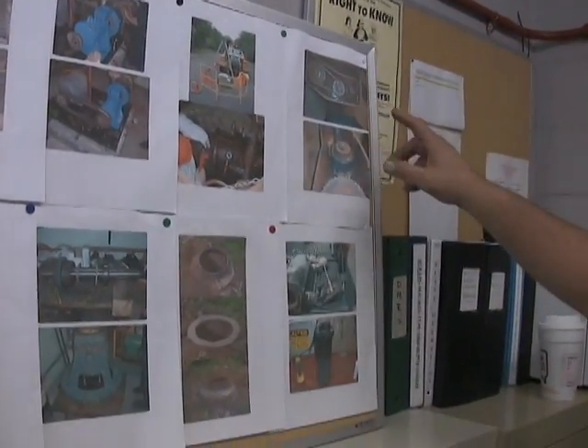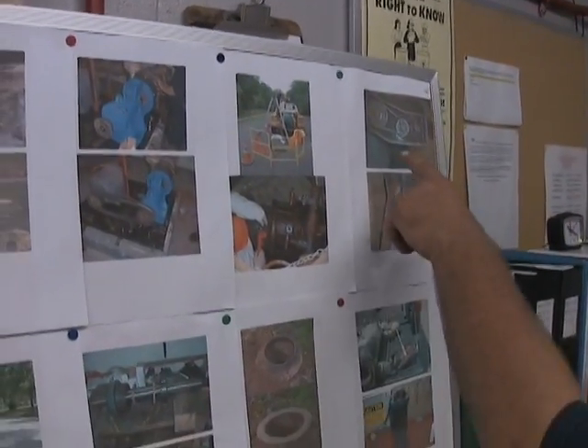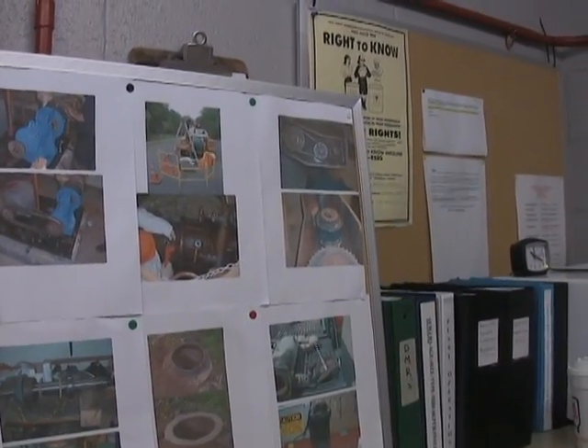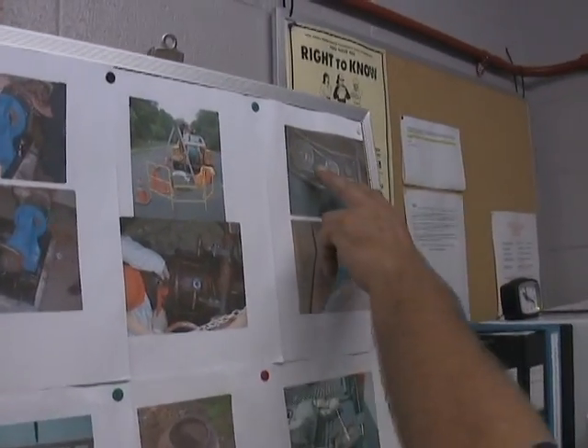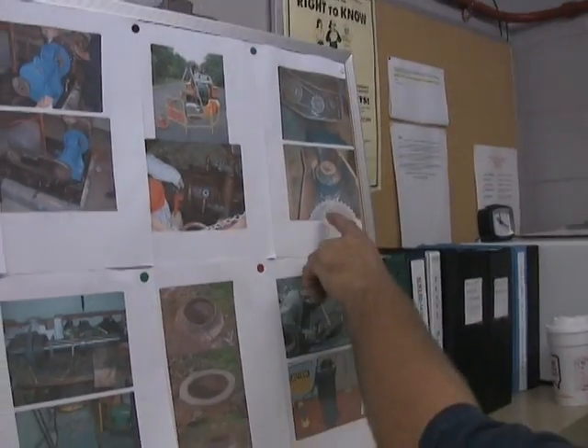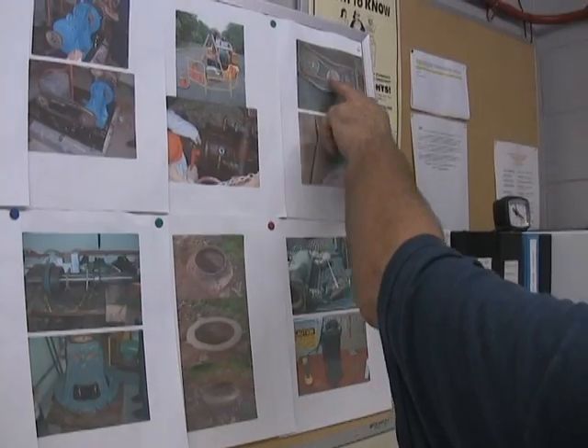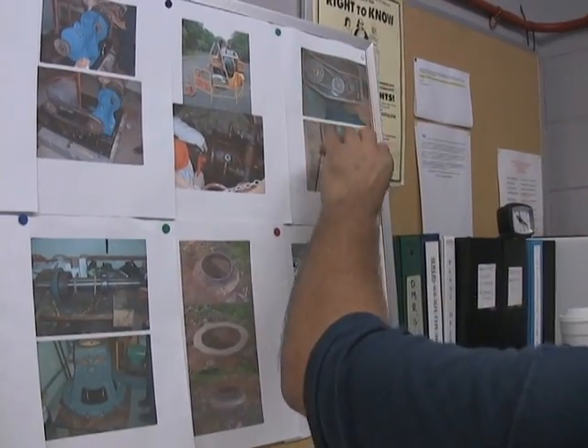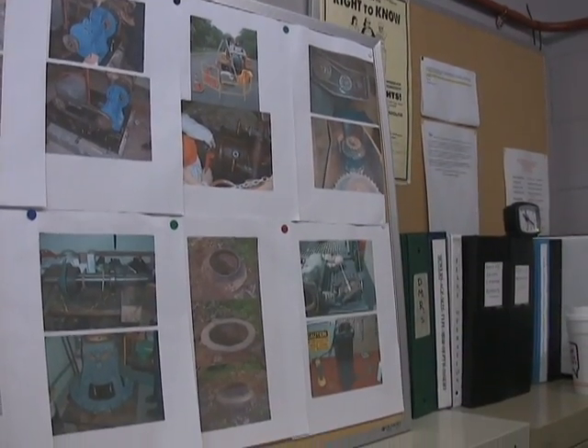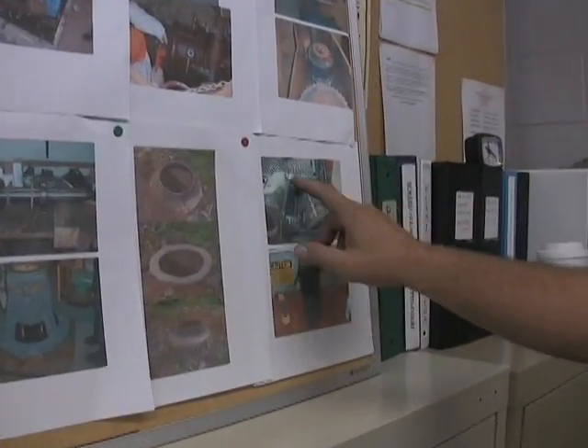Channel Monster. This is actually a recent picture because this came out of Chatham Road and Summit. We found an aluminum sign wedged inside of this thing, and obviously the chain was really bad and off the sprocket. It wasn't working. We brought it down here and redid it all. You're seeing we cleaned this all out, took all the sprockets off, inspected everything, and then put it back together. That's back in and running up in Summit. It's actually filled with sewage. Joe did this here.